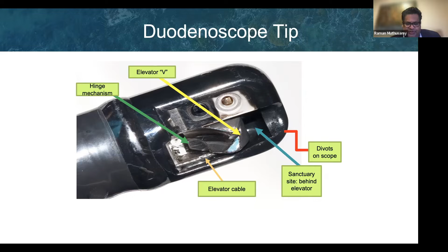And the reason that we run into these challenges is that the cleaning protocols to clean these devices have never been validated in clinical practice. It's usually lab testing. We soil it with a certain amount of bacteria artificially and then assess it in a limited number of cases. And the FDA has said that, as you've seen, user error is well known, but they've commented that user error is part of device design, and if something is too complex to clean, it's up to the manufacturer to make it easier to clean rather than to blame the user.